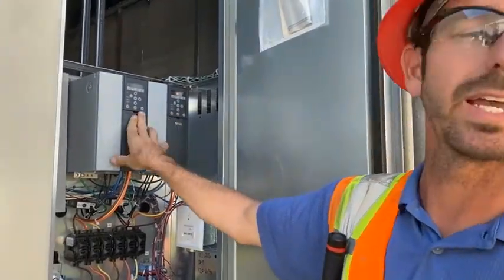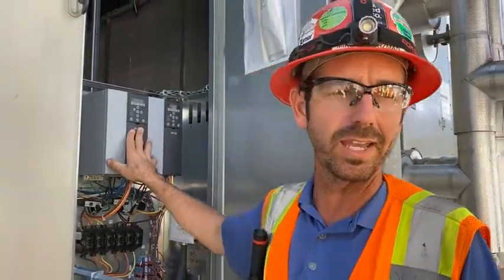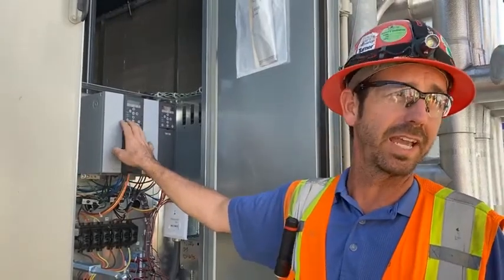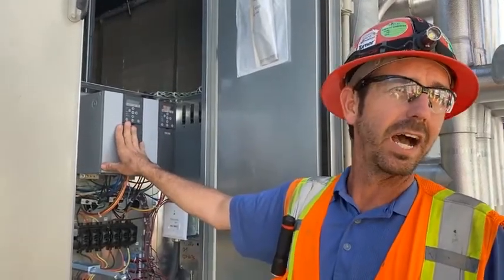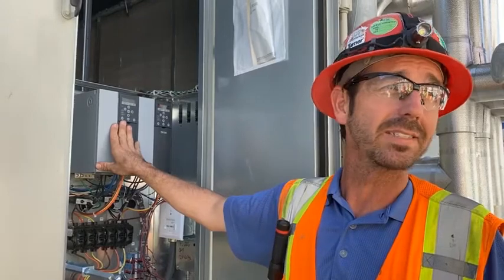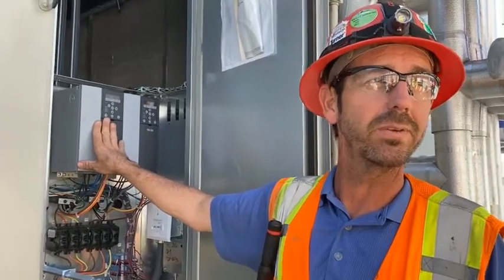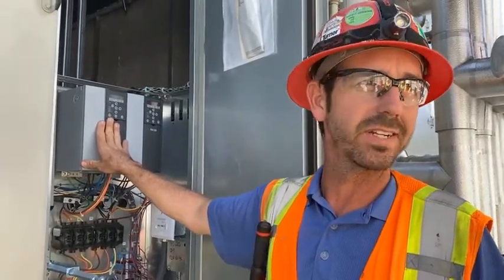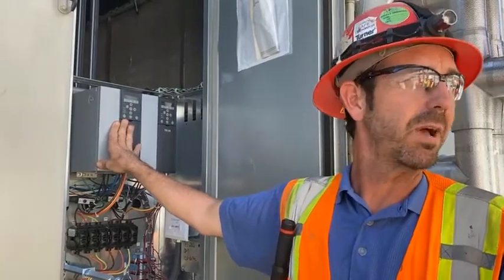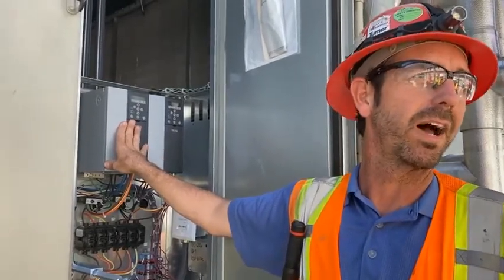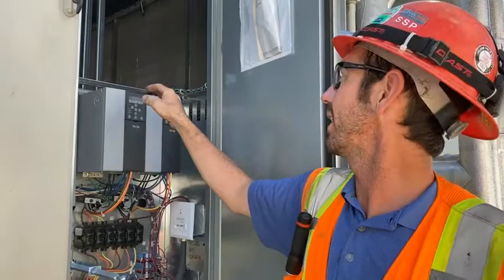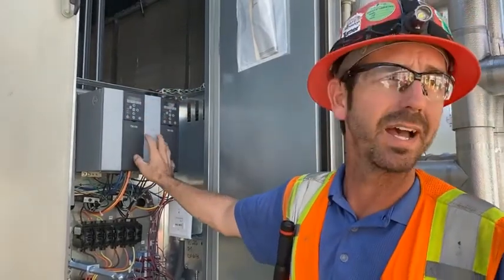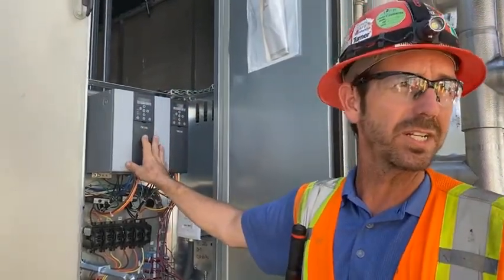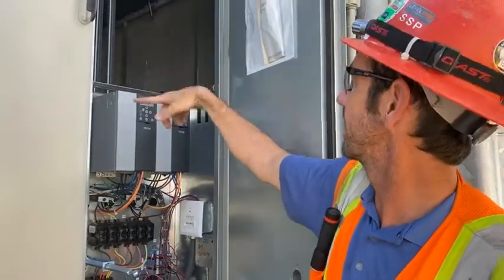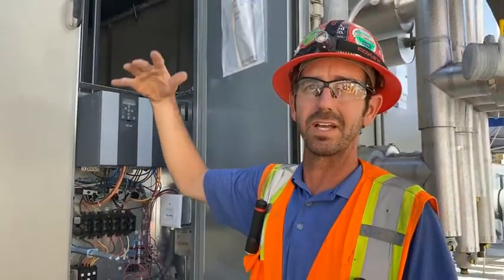So if for some reason, like I said, auto's not working and you can't get that thing to turn on, but you've got to provide cooling, you can turn this in hand. I would definitely not recommend ramping it past probably 45 hertz or so, because we don't know what the boxes are going to do downstairs, okay? But at least that way we're blowing some air through the building while we're troubleshooting why auto's not working, okay? And then, like I said too, make sure you use both at the same time. Right now it's just a demonstration, because right now the air is kind of going to go around in circles in the unit, okay? Because the other fan's not spinning.